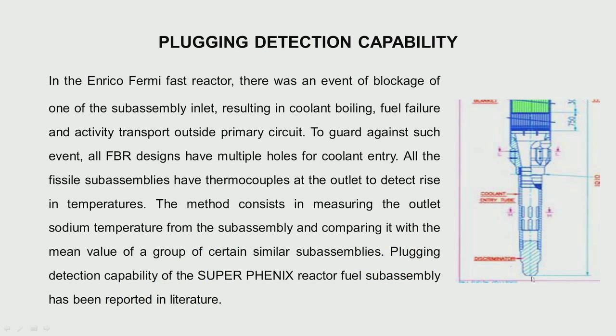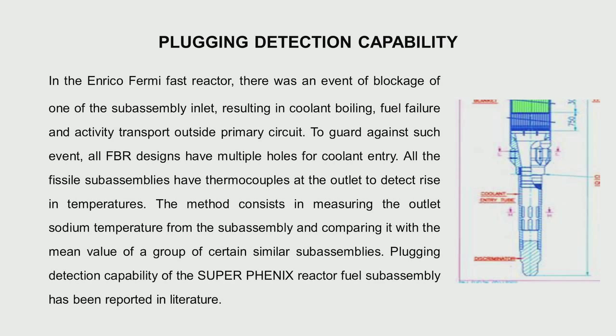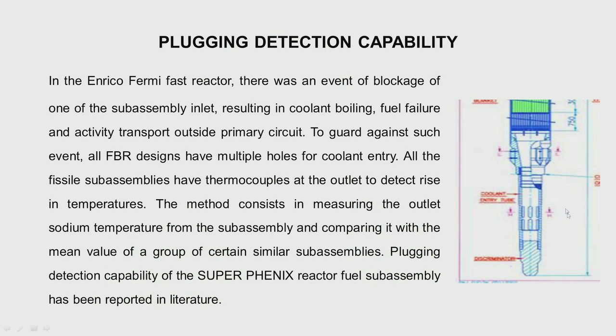They had the fuel assembly with just one entrance — coolant was entering from the bottom — and unfortunately a plate which had detached from somewhere had come and blocked it, maybe not fully. So flow in the assembly was very minimal. With no flow, the sodium started boiling and that sodium boiling gave rise to a negative reactivity, but apparently there was still some flow — not totally plugged. The power and reactivity came down, the operator adjusted it, it went down slightly again, the operator adjusted it again, and finally the fuel had melted. The fuel failure was detected through increased activity in the cover gas argon circuit.